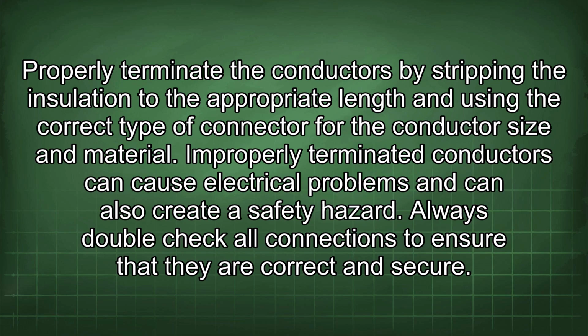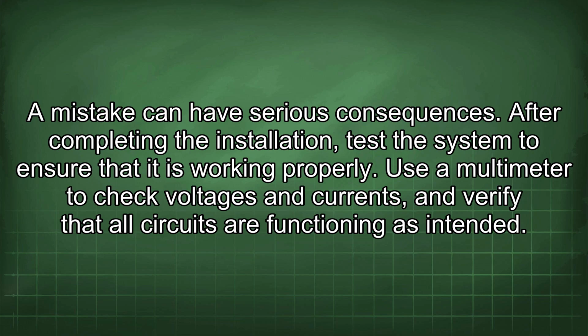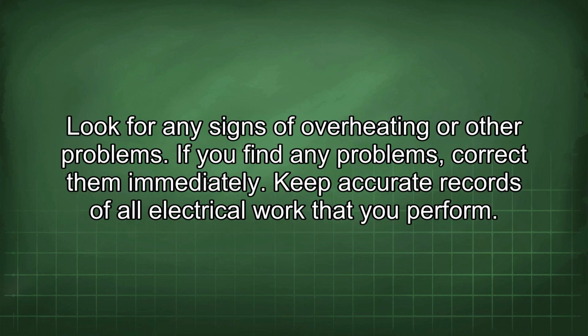Improperly terminated conductors can cause electrical problems and can also create a safety hazard. Always double-check all connections to ensure that they are correct and secure. A mistake can have serious consequences. After completing the installation, test the system to ensure that it is working properly. Use a multimeter to check voltages and currents, and verify that all circuits are functioning as intended. Look for any signs of overheating or other problems. If you find any problems, correct them immediately.